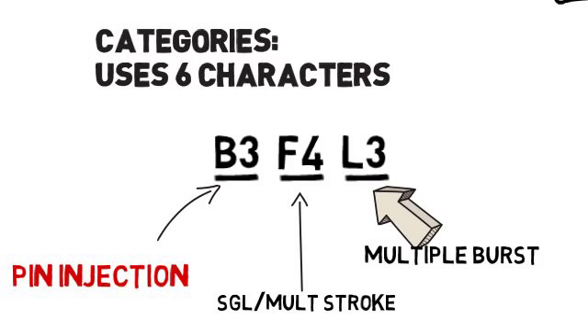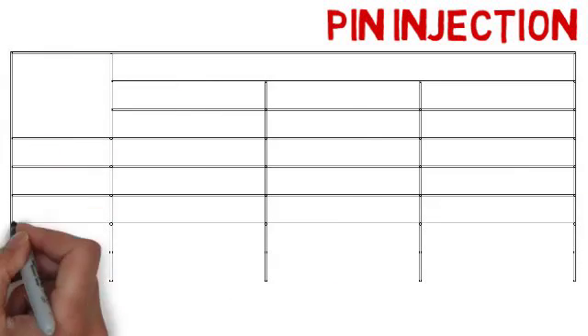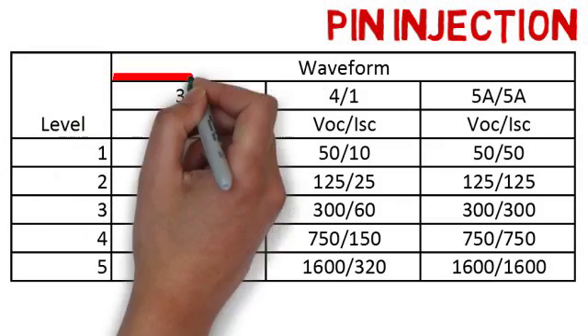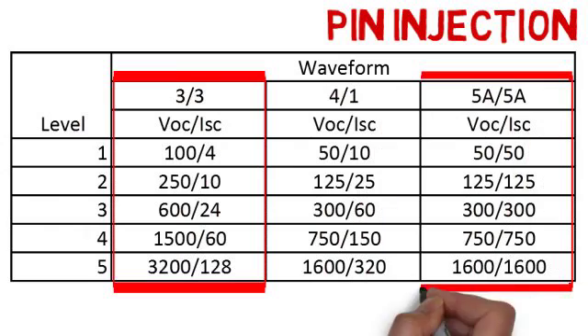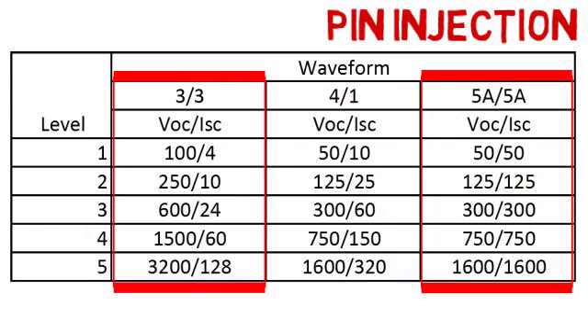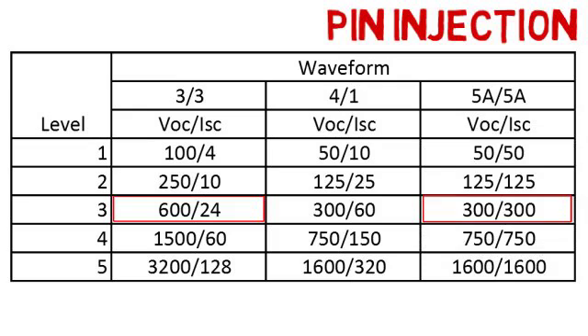Since we're testing to B3 for pin injection, we'll be testing to the B waveform set. This includes waveform 3 and 5A. You can see that at level 3, waveform 3 is 600 volts and 24 amps. Waveform 5 is at 300 volts and 300 amps.